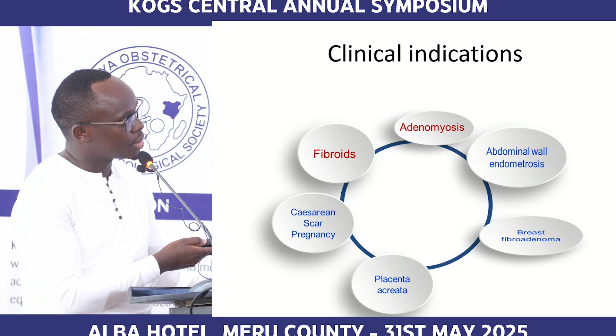So as the name suggests, high intensity focused ultrasound uses basically high frequency ultrasound waves. So it is the same ultrasound machine we use, only that the frequency of this ultrasound is ultrasonic, more than 20,000 hertz. And generally, a transducer emits ultrasound waves, and then they are focused on a point, which is basically a focal point, which acts as the ablative point, or more like a cyber knife. And this convergence of the ultrasound waves, as we're going to see, leads to thermal concentration that hits a point of about 65 degrees Celsius, sometimes up to 100. And this is the ablative point, which causes coagulative necrosis on the tissue that you are targeting. In this case, we are talking about fibroids.